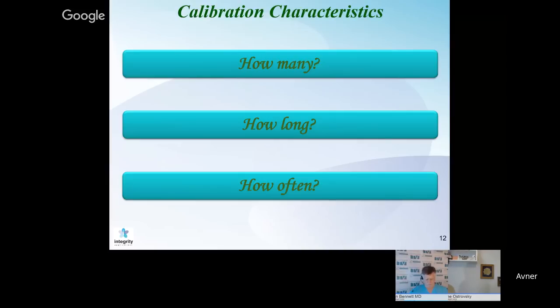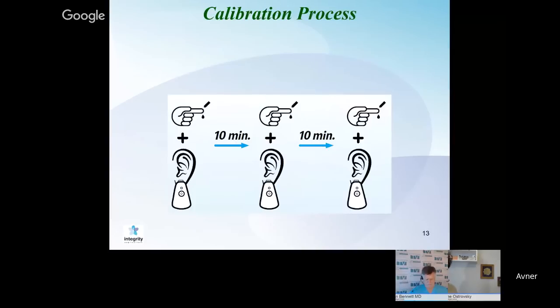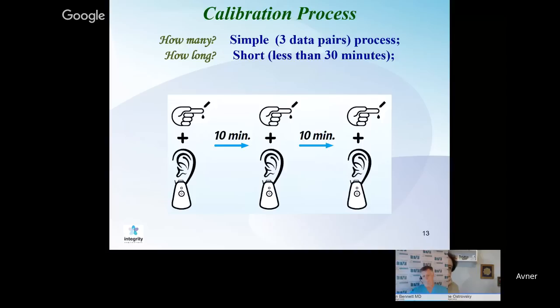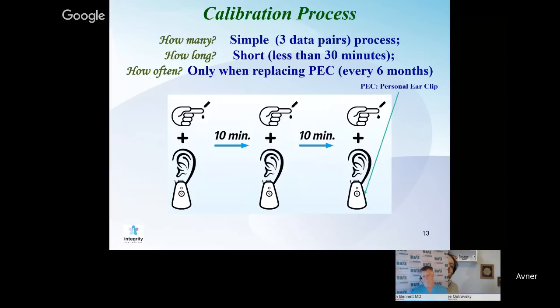And here is the big news of GlucoTrack. So this is how the calibration is done. We make 3 pairs of invasive measurements plus measurements with our device, at 10-minute intervals. So let's answer the questions. How many? A process that requires only 3 data pairs. The whole process takes less than 30 minutes. And the most important, how often? Every 6 months we have to replace the ear clip. With the new ear clip, the calibration is valid for the entire 6 months. So to make a long story short: twice a year, half an hour, 3 prickings, that's it. And then from that point on, you can monitor yourself as many times as you like. Actually, the whole idea of the device is to encourage you to monitor yourself as many times as you like. No limitation, no blood, end of story. Very simple.